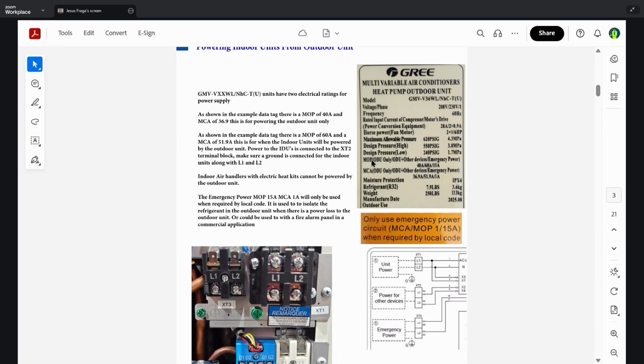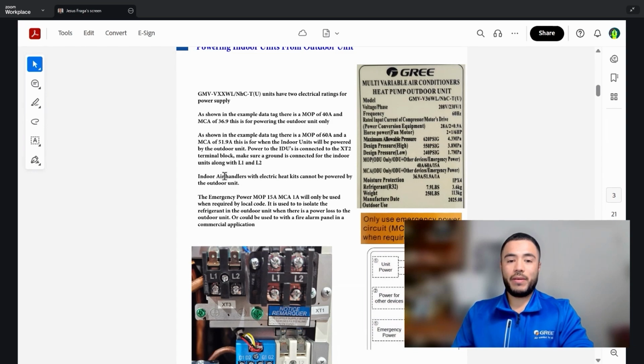As we see here, we have MOP, ODU only, 40 amps. Other devices means the indoor units, and that's 60 amps. Emergency power is 15 amps. We will talk about emergency power later on in this quick start guide. As I stated earlier, for units that are utilizing heat kits, this will not be applicable, as the heat kits do pull more amperage, and the wire supplied from the outdoor unit to the indoor units will not be able to support the heat kit once it is engaged.